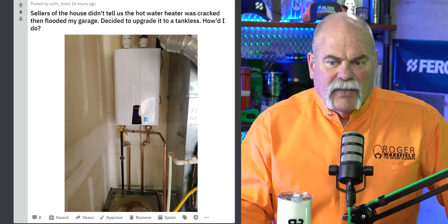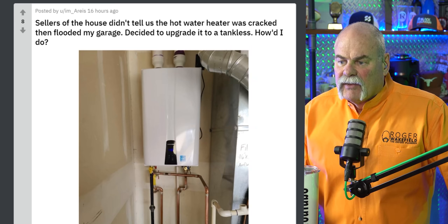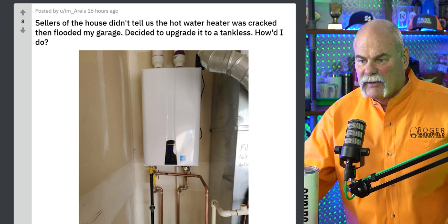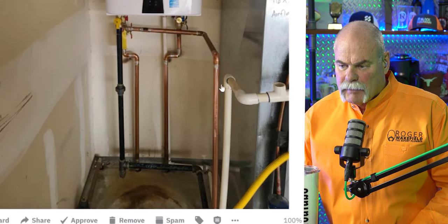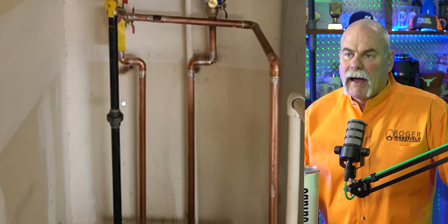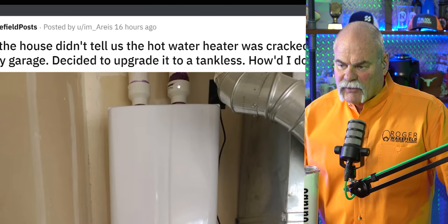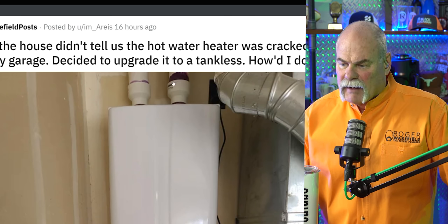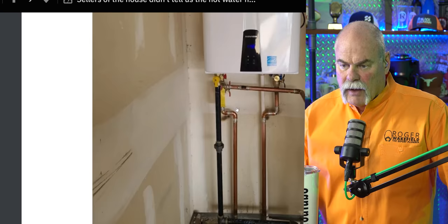So here's another one. Sellers of the house didn't tell us the water heater was cracked, then flooded my garage. Decided to upgrade it to a tankless. How'd I do? I gotta tell you, it looks like the install is pretty clean. I don't see a lot of problems. Looks like the T&P has a drain on it. You've got valves there for flushing. Gas pipe is hard pipe — I love that. So many people are on the flex connectors these days. It works. The only problem I see is there's a ton of primer right there. But if that is the only thing you did wrong, this is a really good install. Hats off to you.